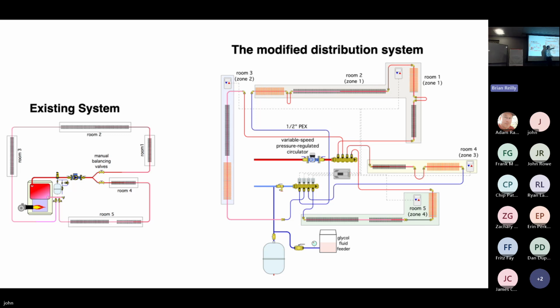And this is just a standard relay controller. Taco makes some, Caleffi makes some, a lot of Honeywell makes them. And then they all go up to thermostats. So what we've got now on this distribution system is 4 independent zones, all controlled by electronic thermostats. And this controller would have an output so that when any zone thermostat calls for heat, it can close a relay contact, which can trigger a heat source to operate. So I haven't even put the heat pump into the picture yet. I'm just saying, let's put it on the operating table, convert it over to this.